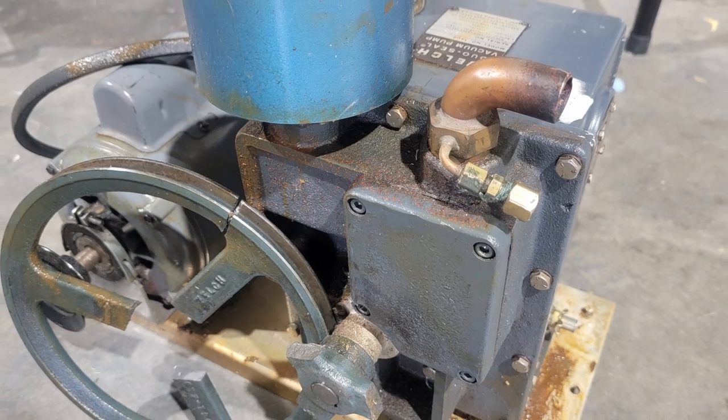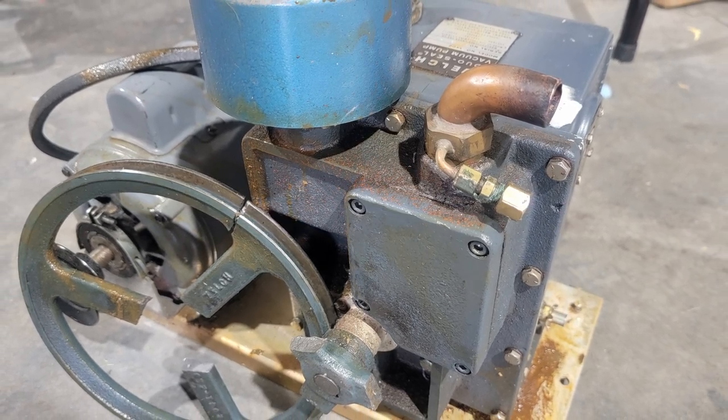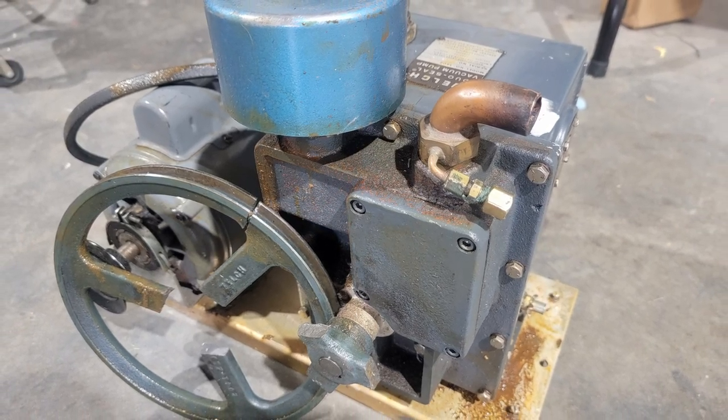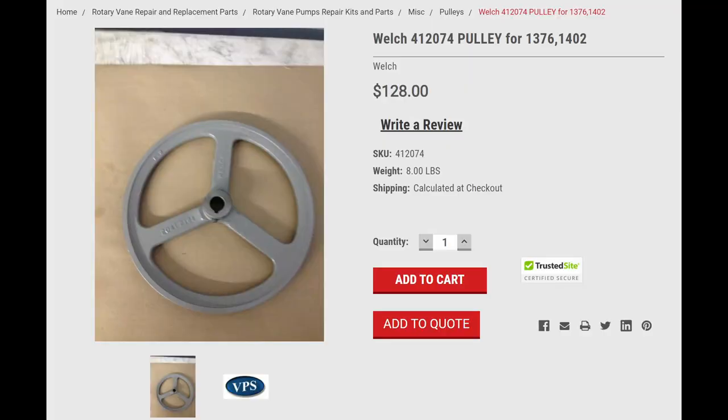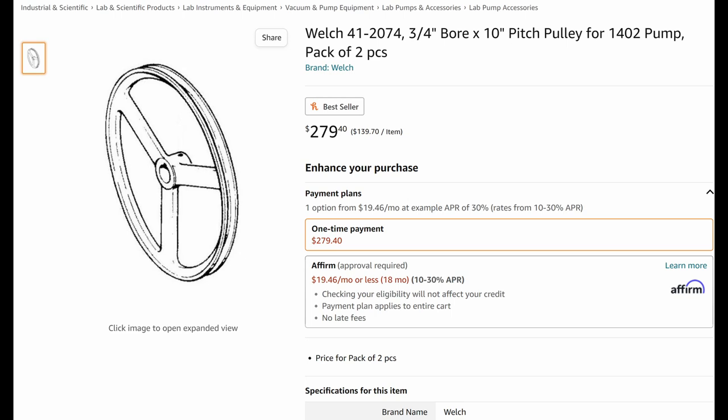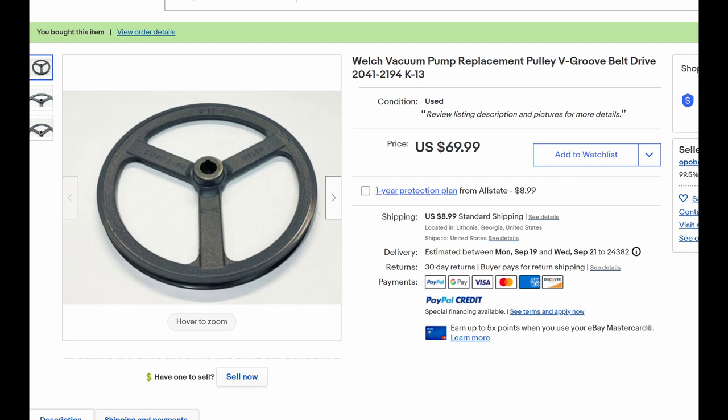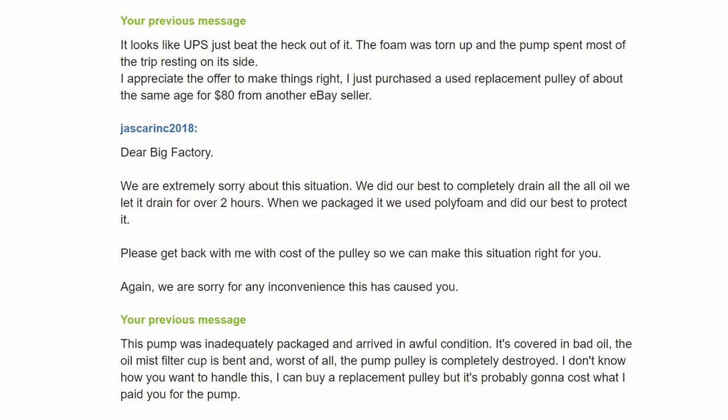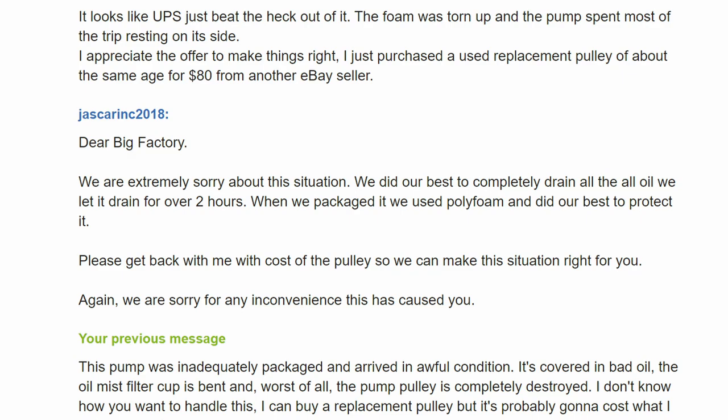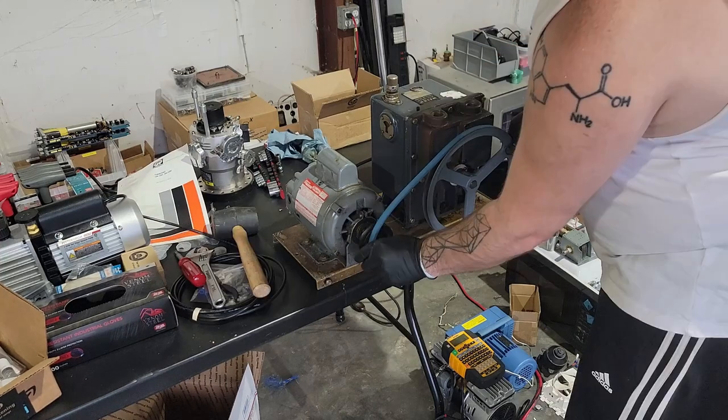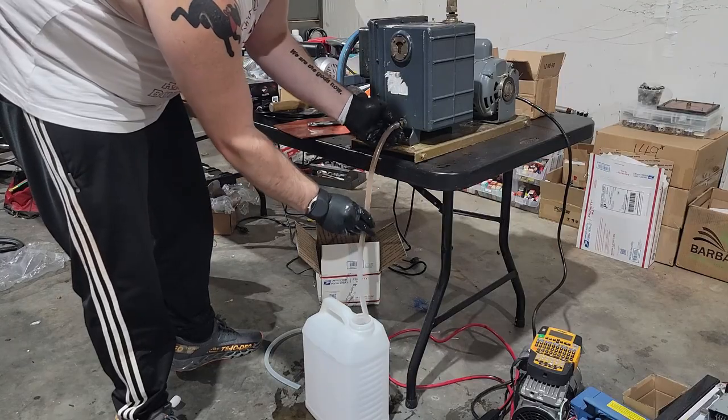Unfortunately, they weren't able to drain all of the oil out of the pump before shipping it, and they just had no idea how to pack it for shipping. So by the time it made it to my house, FedEx had beat the absolute hell out of it. The thing was just covered in dirty vacuum oil. The original oil mist filter was completely bent up, and worst of all, the cast iron pulley on the pump body itself had been cracked in half. I checked all the usual suspects for a replacement pulley, Ideal Vac, Lesker, etc. A brand new replacement pulley for a Welch 1402 Duo Seal costs more than I paid for that pump. Luckily, I found someone on eBay selling a replacement pulley for like 80 bucks, so I contacted the original seller of the pump and asked them if they'd be willing to reimburse me the amount that it would take to replace the pulley, and shockingly, they did. So after cleaning up the Welch, replacing the pulley and the belt, and doing a flush and an oil change, it worked fine.